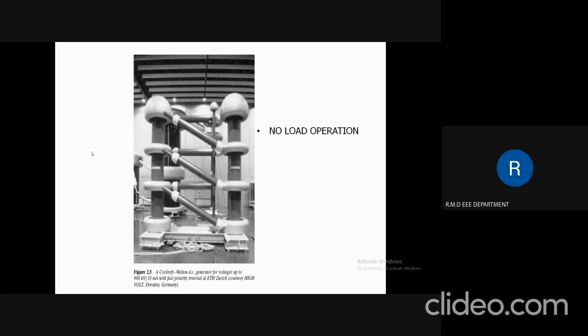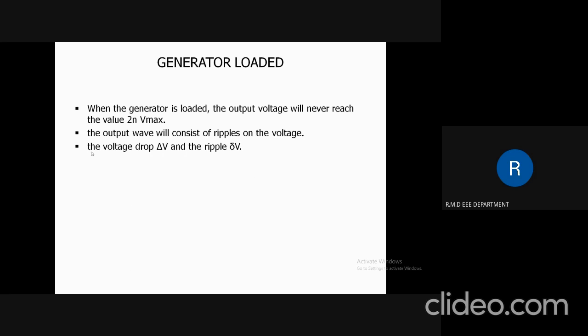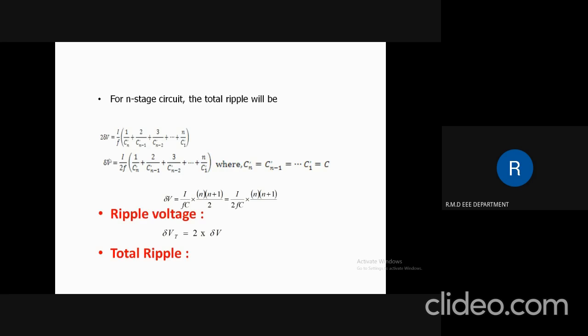This is the practical view of the Cockcroft voltage DC generator circuit. Under loaded condition, when the generator is loaded, the output voltage will never reach 2N × Vmax. The output will consist of ripples, and the voltage drop delta V and the ripple voltage are represented as delta V. For an n-stage circuit, the total ripple is represented as: delta V = (I / FC) × N(N+1)/2, which equals I / (2FC) × N(N+1).